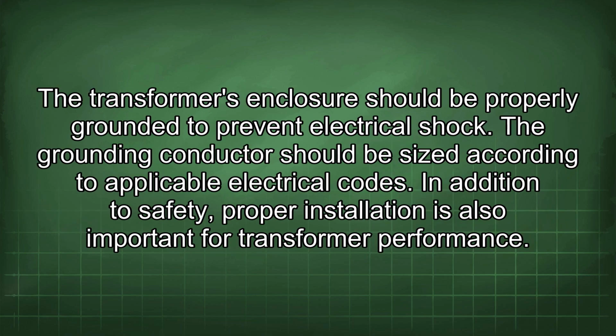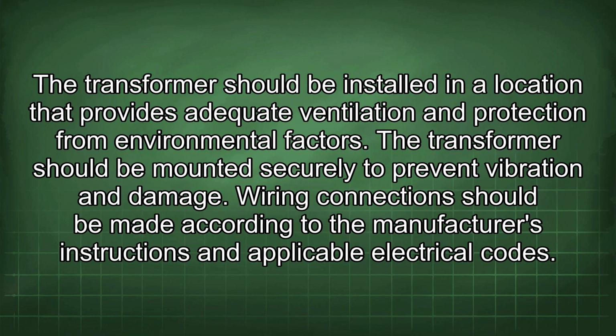The transformer's enclosure should be properly grounded to prevent electrical shock. The grounding conductor should be sized according to applicable electrical codes. In addition to safety, proper installation is also important for transformer performance. The transformer should be installed in a location that provides adequate ventilation and protection from environmental factors. The transformer should be mounted securely to prevent vibration and damage. Wiring connections should be made according to the manufacturer's instructions and applicable electrical codes.